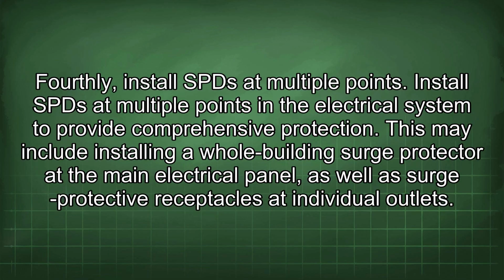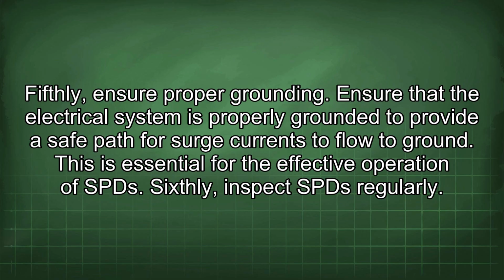Fourthly, install SPD at multiple points. Install SPD at multiple points in the electrical system to provide comprehensive protection. This may include installing a whole building surge protector at the main electrical panel, as well as surge protective receptacles at individual outlets. Fifthly, ensure proper grounding. Ensure that the electrical system is properly grounded to provide a safe path for surge currents to flow to ground. This is essential for the effective operation of SPD.